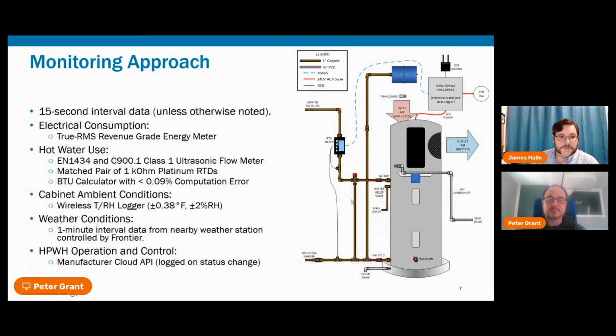We also logged ambient conditions in the cabinet at 1-minute intervals, with the sensor placed so that it could effectively capture the inlet air temperature of the evaporator. We also monitored the outdoor weather conditions from a nearby weather station that we controlled so that we could control the logging rate. All of this was uploaded every hour from all 10 closets via cell modems to our monitoring server, which also performed an automated daily performance analysis.